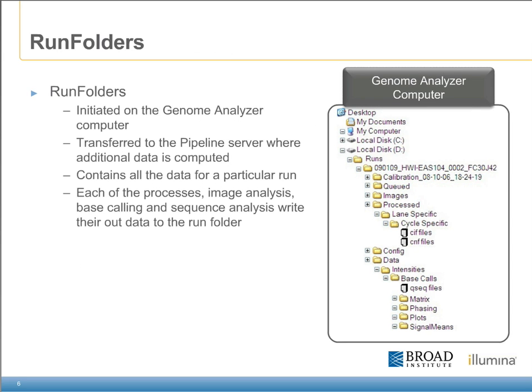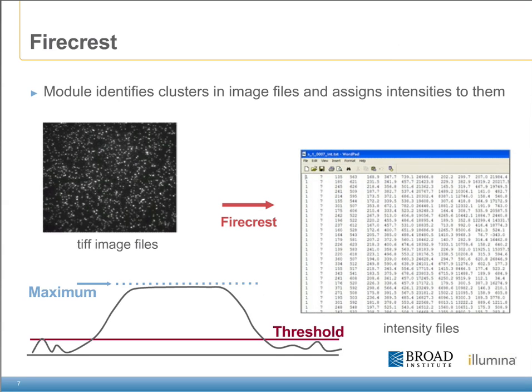The following is an example of a run folder structure produced on the GA. It contains both the lane-specific information as well as the cycle-specific information that is eventually transferred to the network location. One of the initial tasks of the primary analysis is to develop the cluster locations based upon the raw TIFF images developed from the GA. The software translates peaks of intensity against a background into a table to determine the overall intensities for each base at each cluster location throughout the run. This module is called FireCrest and exists both within the RTA as well as the complementary section of the pipeline software package.